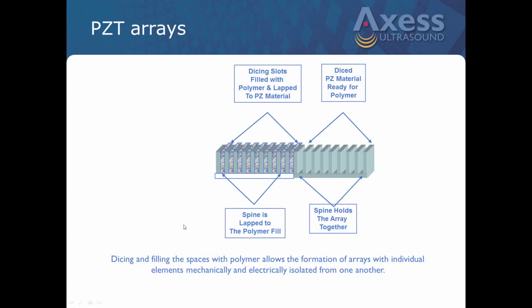Again, one of the things that are used nowadays in the PZT arrays is called dicing. And essentially they go through with a very, very fine, for lack of a better word, circular saw. And they actually cut these arrays. They fill them in with either a polymer or some type of epoxy material. And they do what's called a dicing process. And they have to put a spine back here along this edge, which actually holds the elements together. And then that forms what we call the array stack, or what you would see in the probe is the actual array itself with the lens.